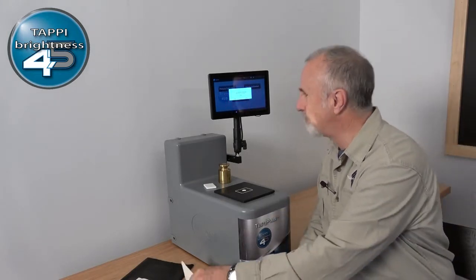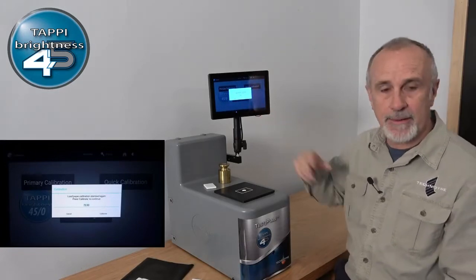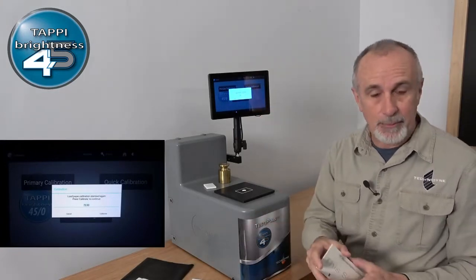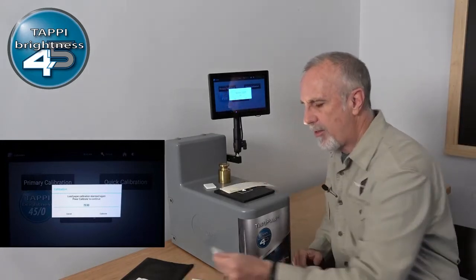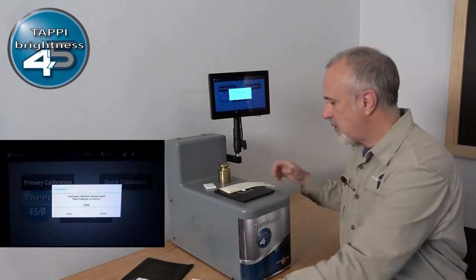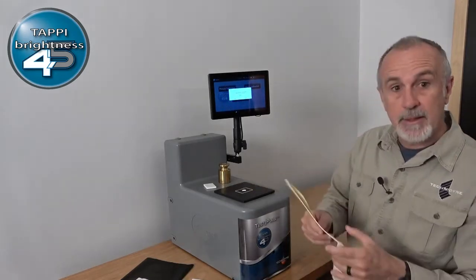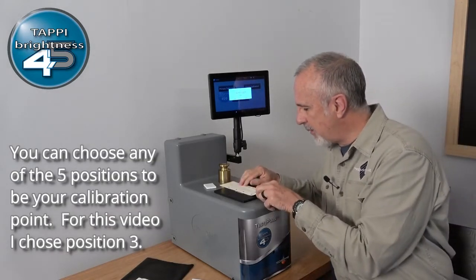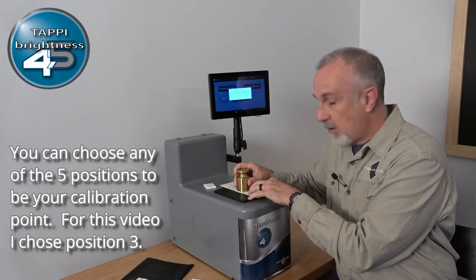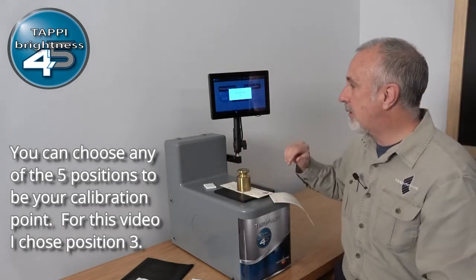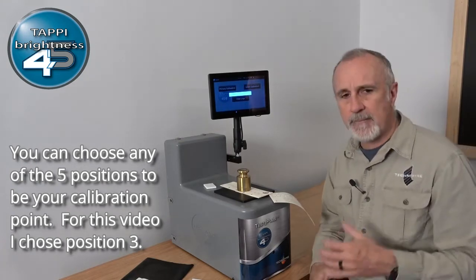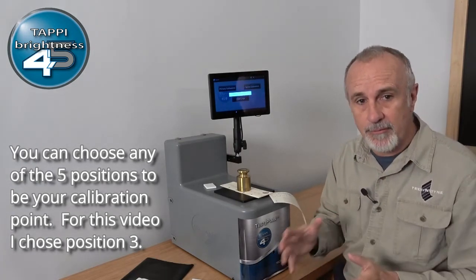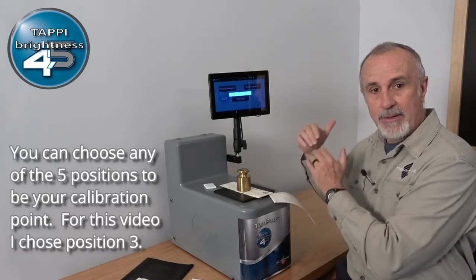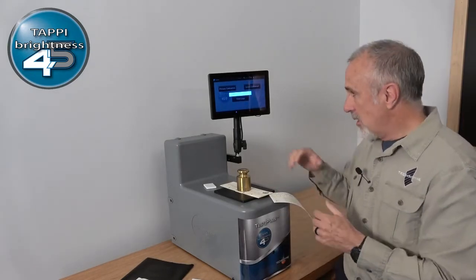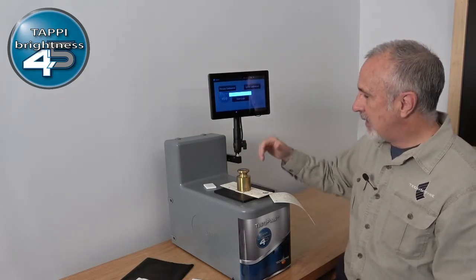Okay, so there is a value in here, and that value I had already put in because I had previously done the calibration. That value is associated with the third position value on my paper tape. So I will take this machine direction like this. I will load the sample into position 3, load it with the 1 kilogram weight, and hit the calibrate button. Then the instrument is going to go through the calibration sequence of all the different functions, and then it's going to tie this instrument back to the master instrument back in our master's lab. All right, so it's stepping through that sequence, and as it does that, it will complete that process.